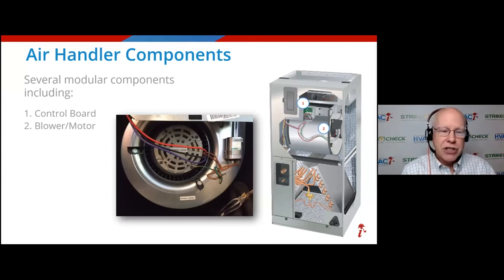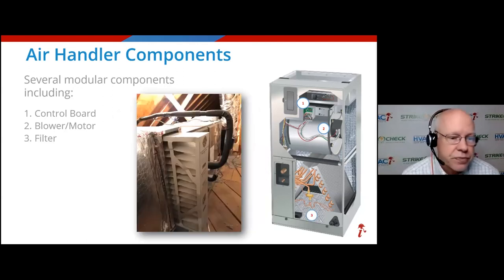These things are modular. If you look at that photo, you can't see the third screw, but it's up there at the top, it's hidden. If you have access to this and you're a qualified technician, three screws, three or four wires, take it out, put a new one in, which you can get, and you've put a new blower motor in less than 30 minutes, right? And you didn't pay for an entire HVAC system. And that shows up on reports all the time as well, because motors are inherently susceptible to losses, and sometimes they just wear out as well.